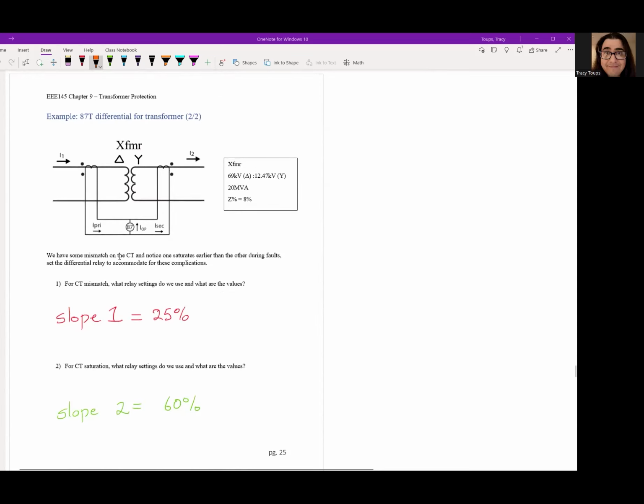Next thing you want to do is let's talk about some slope settings. So again, remember, we're going to have a problem with CT mismatch, and in case one of them saturates before the others for external faults. So for CT mismatch, we have a slope 1 setting, which is typically about 25%. And after a certain point, a slope 2 setting will come into effect at 60%. And honestly, I forgot to mention this. I don't think you could choose where slope 1 and slope 2 start. I think that's typically hard coded into the relay itself.